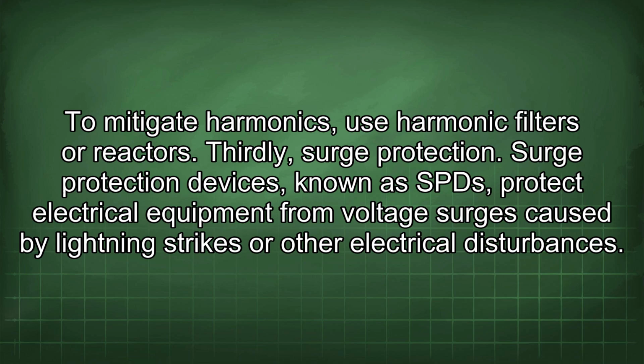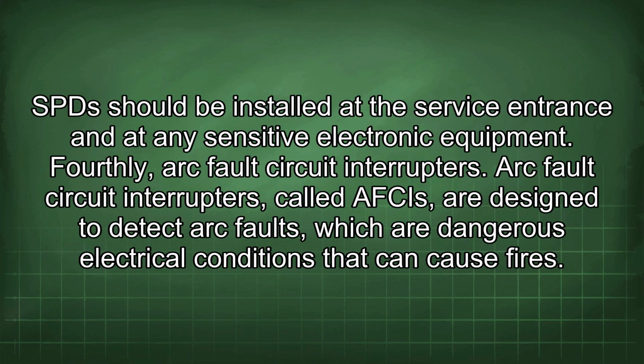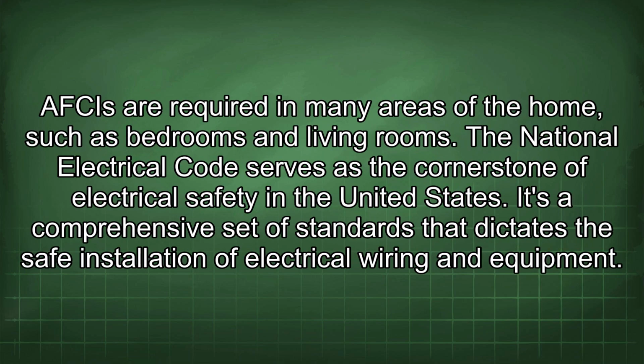Thirdly, surge protection. Surge protection devices, known as SPD, protect electrical equipment from voltage surges caused by lightning strikes or other electrical disturbances. SPD should be installed at the service entrance and at any sensitive electronic equipment. Fourthly, arc fault circuit interrupters. Arc fault circuit interrupters, called AFCIs, are designed to detect arc faults, which are dangerous electrical conditions that can cause fires. AFCIs are required in many areas of the home, such as bedrooms and living rooms.